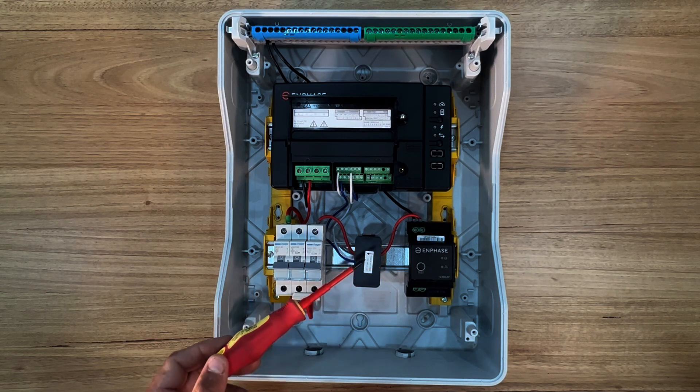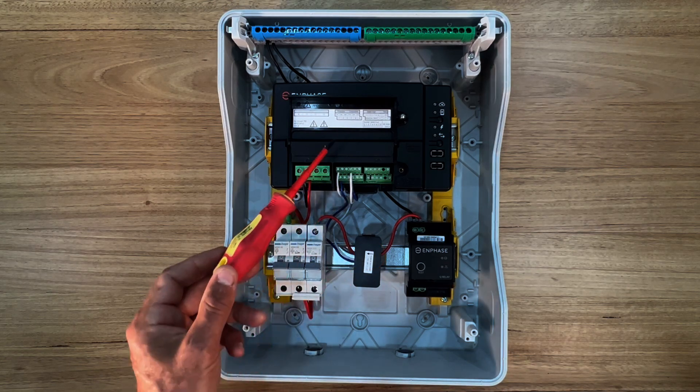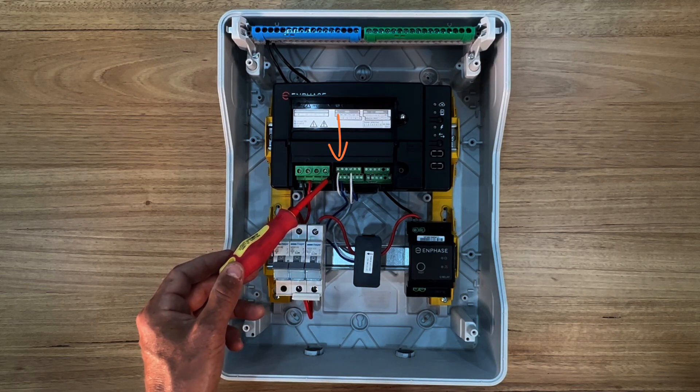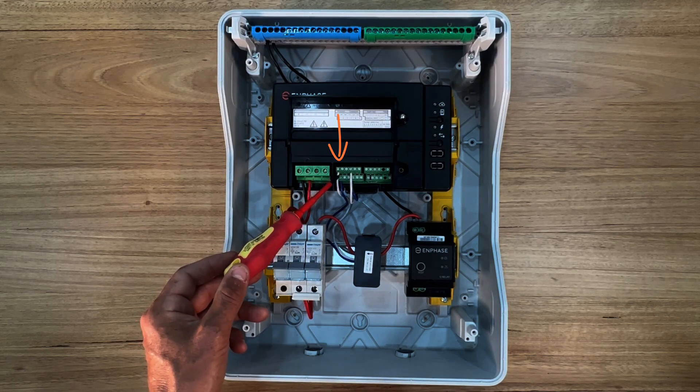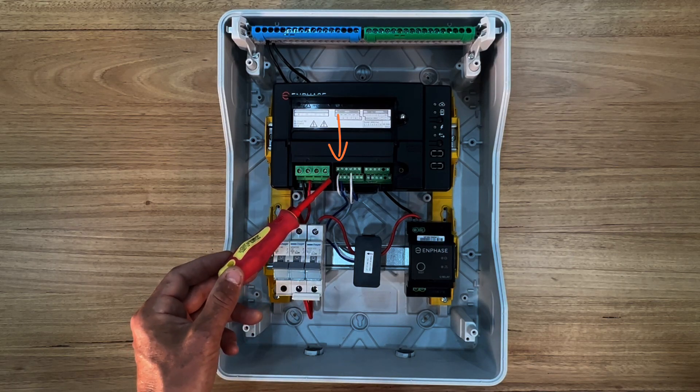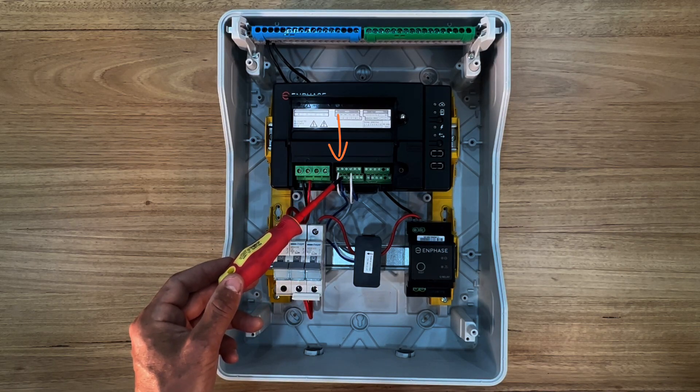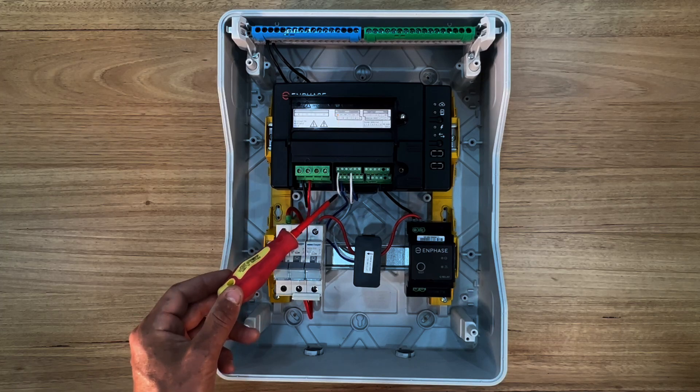The production CT is connected to the L1 CT terminals at the IQ gateway. Note that white always connects to the top terminal and blue connects to the lower terminal.